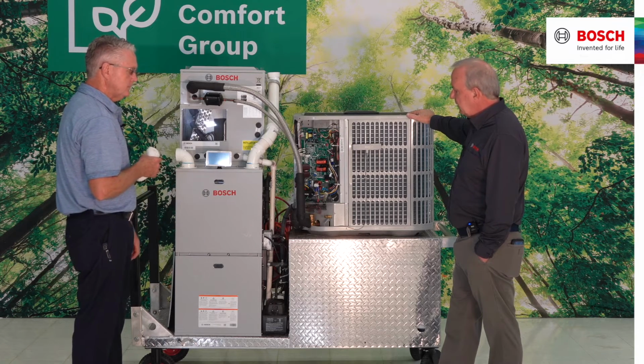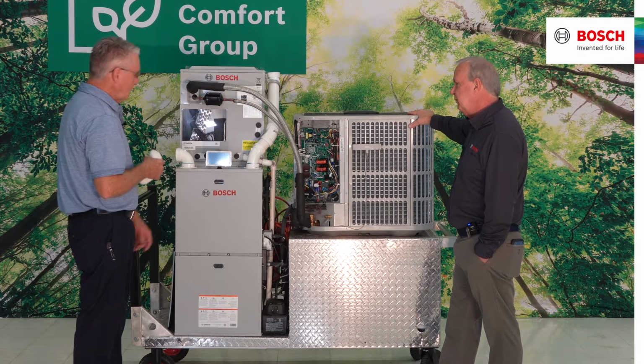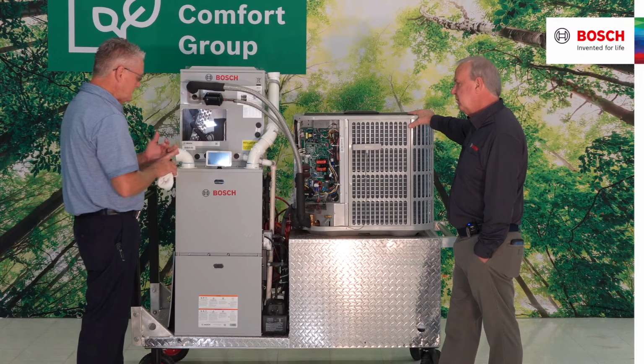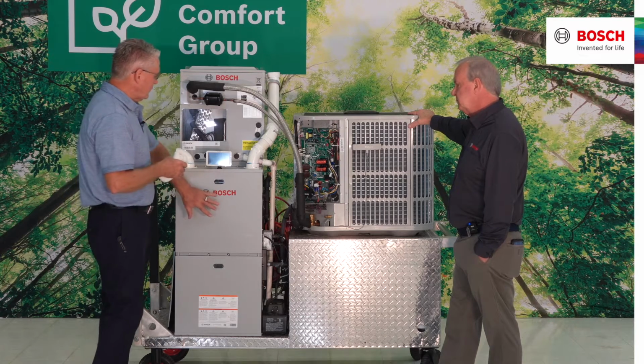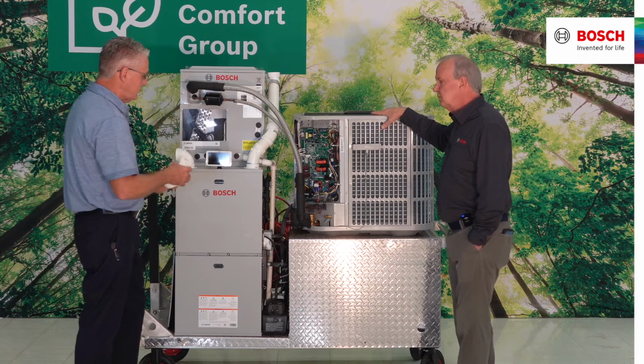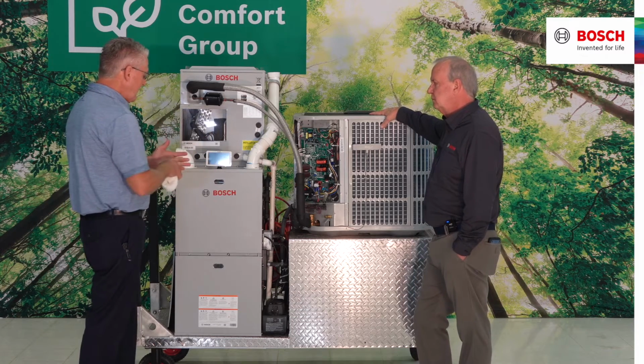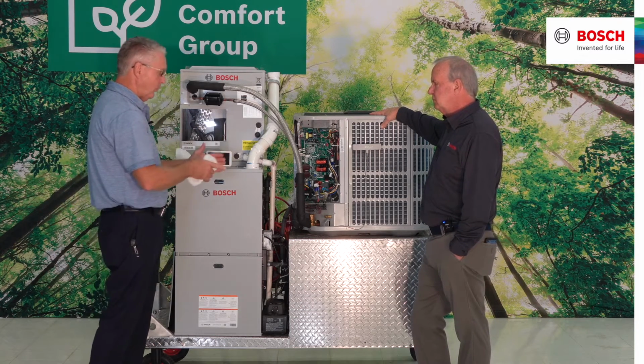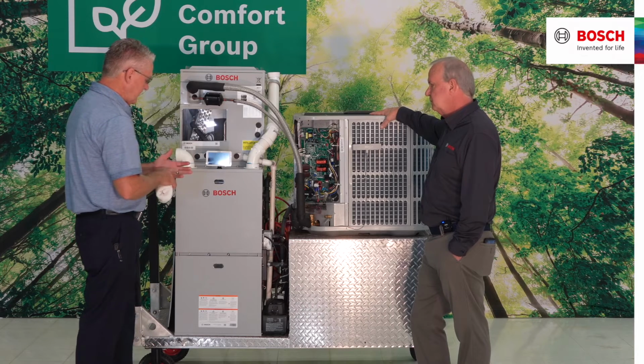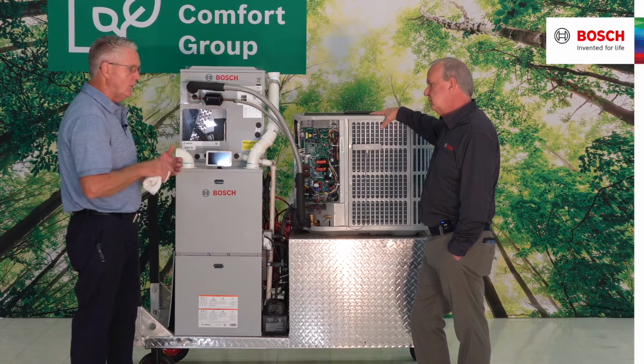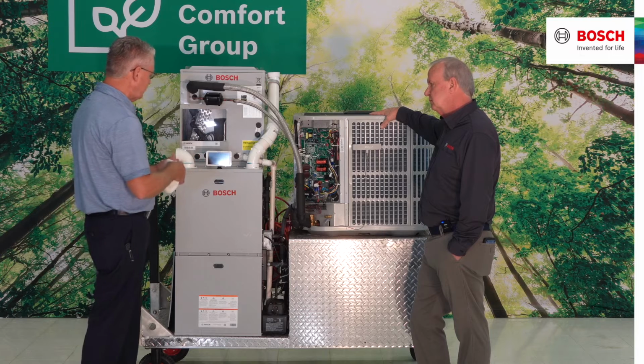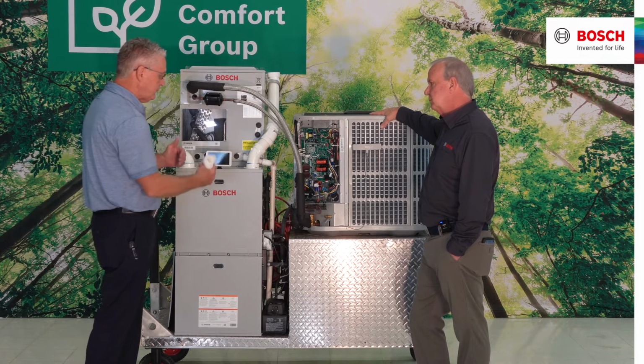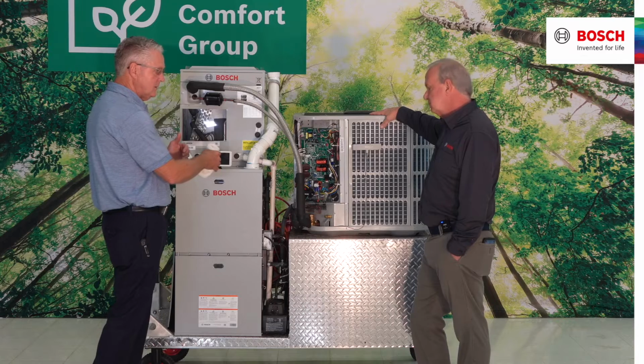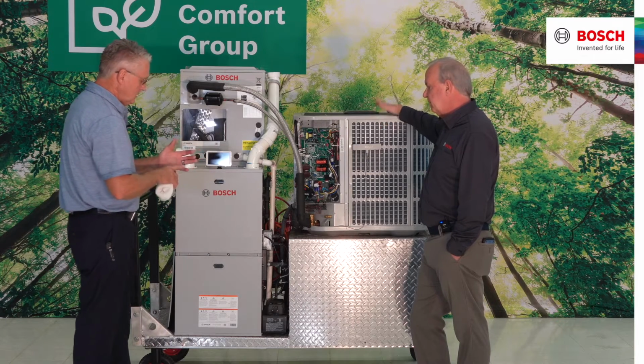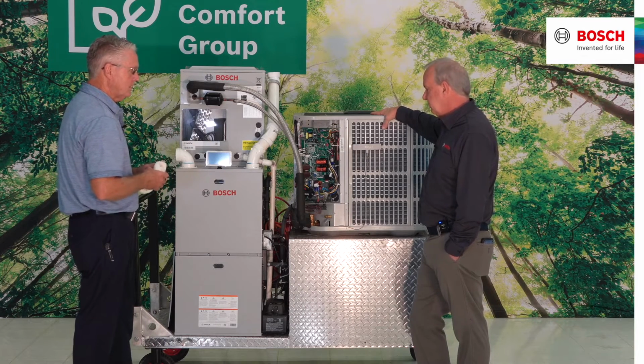Okay. And we have multiple stages as far as the heating mode goes? We have a 2-stage gas valve. So that means that if this furnace was an 80,000 BTU on the model number, half of that would be 40,000. So when I'm in a W1 low fire situation, the output is only going to be 40,000 of the 80. Half of that, yes, half, sir, of whatever the total BTU.